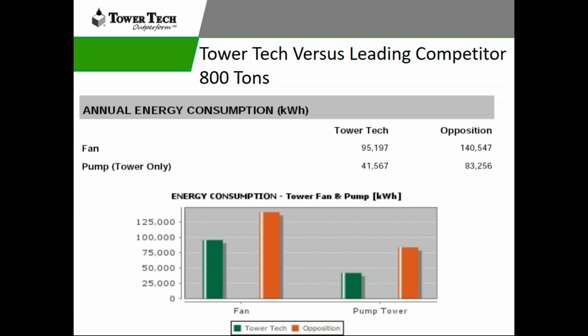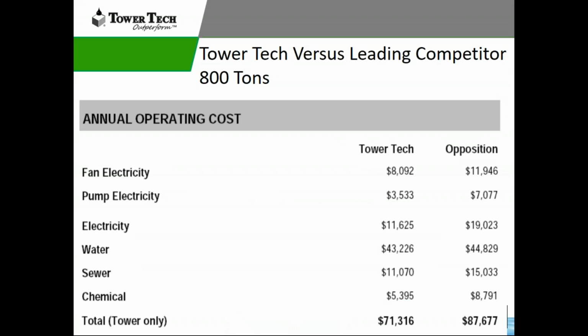And then from a fan consumption kW, we're saving significant energy on the fan system because we could operate at part load. We could operate at lower horsepower on the fan system. So 95,000 versus 140,000. And then when we do the full analysis on an annual operating cost, it's about $16,000 a year energy savings and water savings versus a traditional cooling tower system.